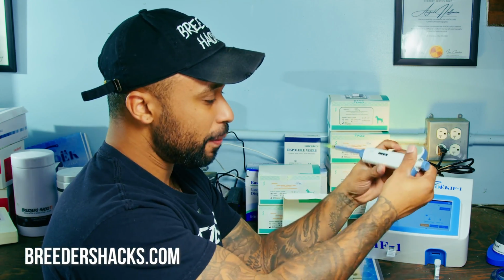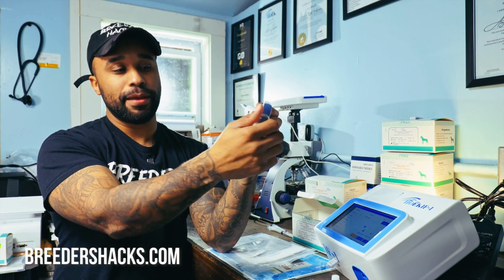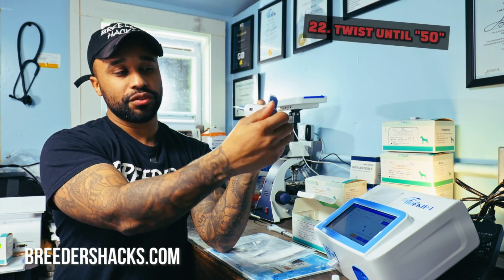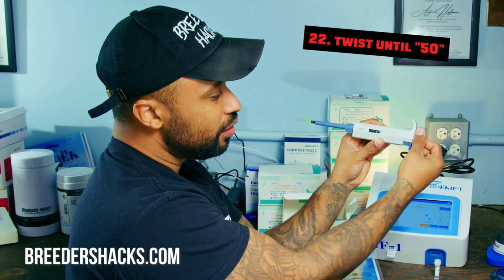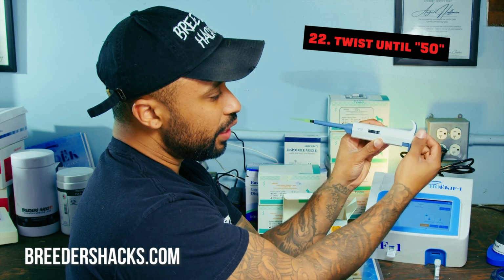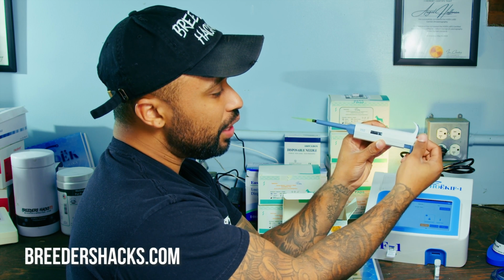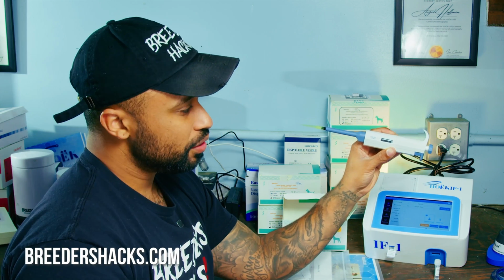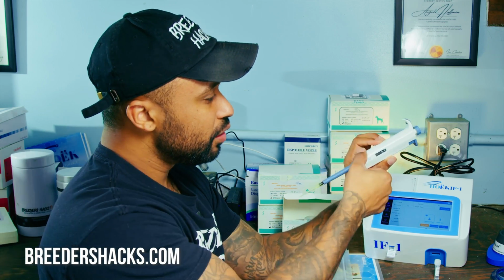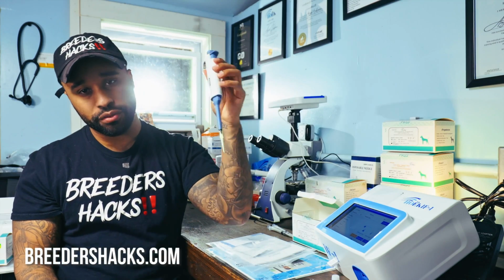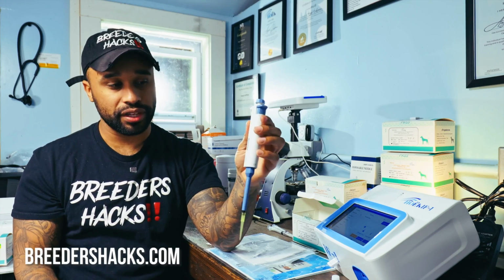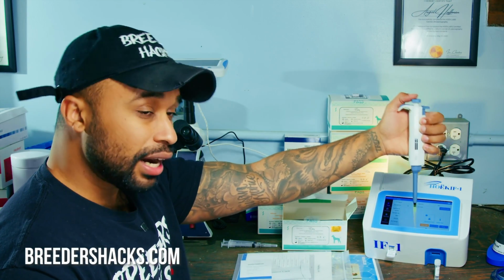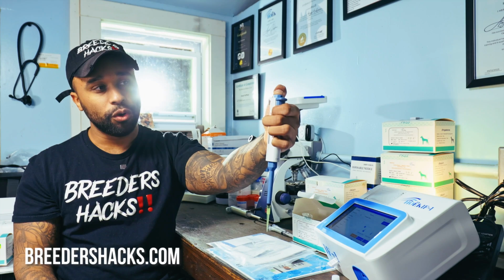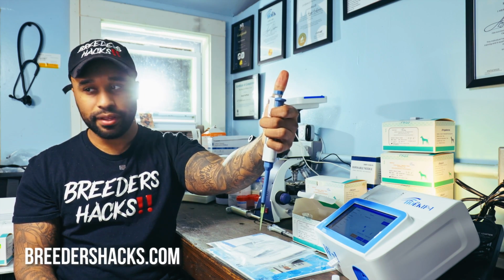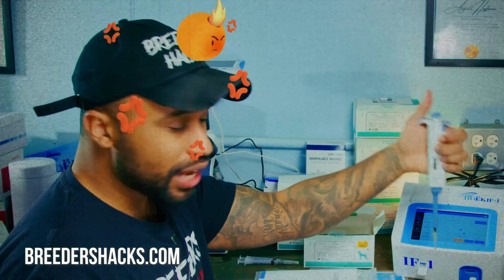So here we go, I'm going to show you. Because this is an adjustable pipette, what you're going to do is twist it all the way to the number 50, because we're going to take out 50 microliters of serum. Now that we're at 50, we're ready to extract 50 microliters from the sample. But there's one other thing: when you press down on the stop, a lot of people will press all the way down and lift all the way up. That is completely wrong, and you will not get accurate results — your test results will probably be wrong.